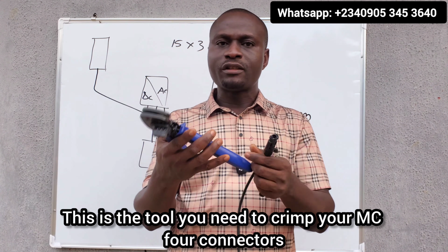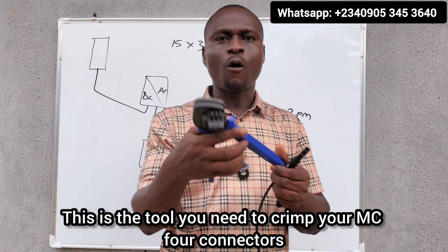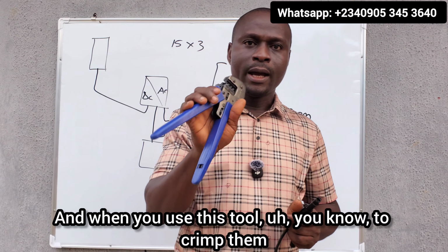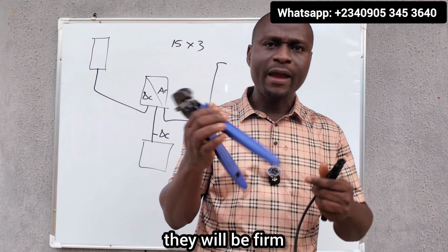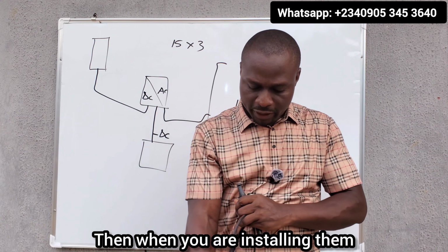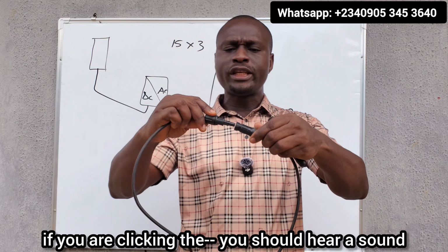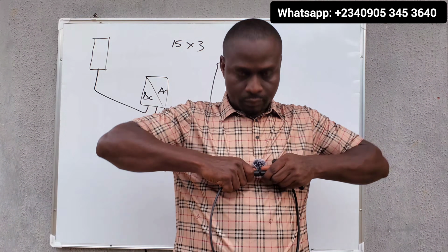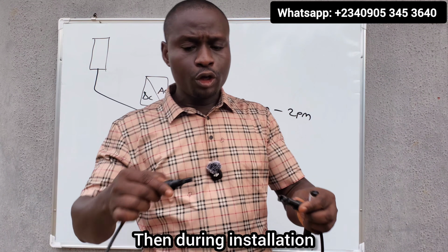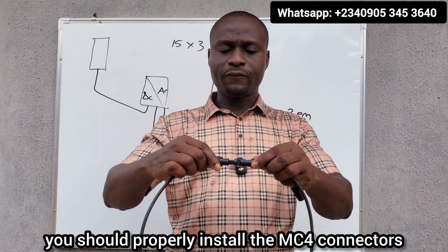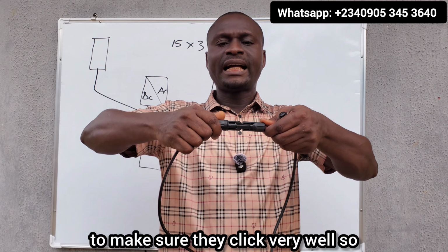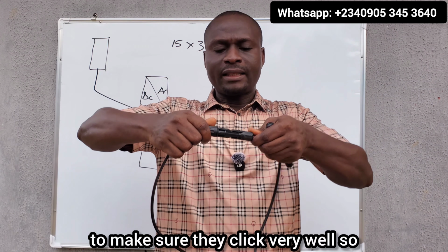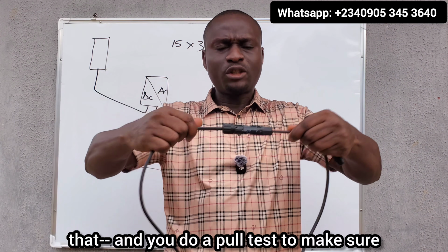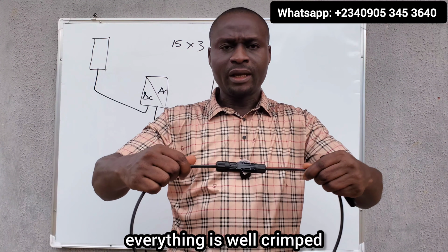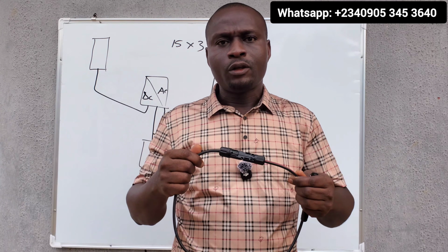This is the tool you need to crimp your MC4 connectors. When you use this tool to crimp them, they will be firm. Then when you are installing them and clicking, you should hear a sound. During installation, you should properly install the MC4 connectors to make sure they click very well, and then do a pull test to make sure everything is well crimped. Nothing should pull loose, you have to be sure.